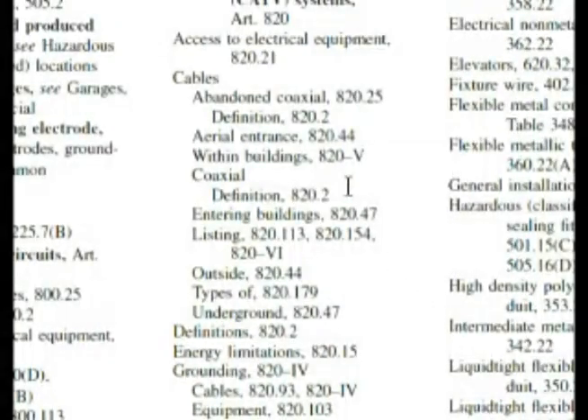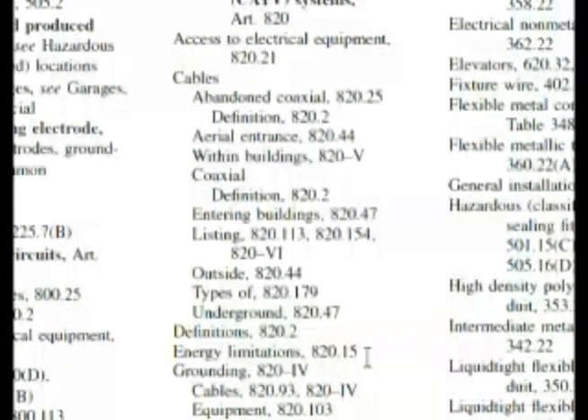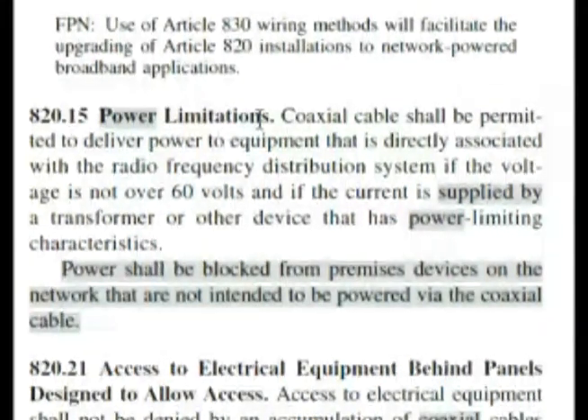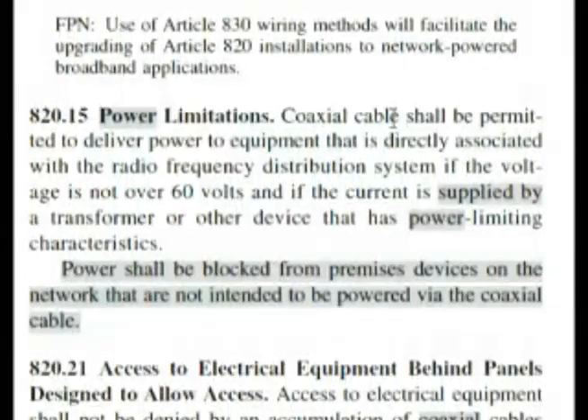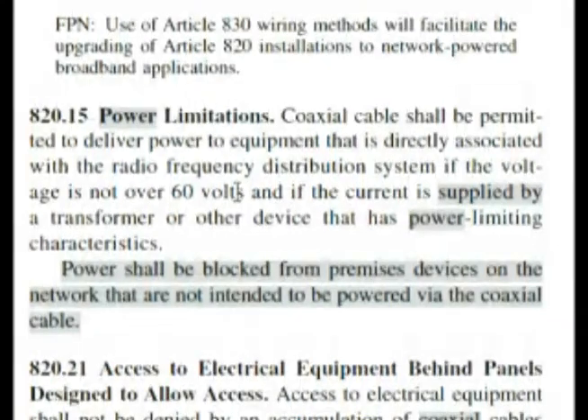Now remember when I said 'power limiting device'? Let's go down a little bit. As we're looking, here it is — energy limitations, 820.15. Here we are in our code book at 820.15 power limitations, and this is almost word-for-word: coaxial cable shall be permitted to deliver power to equipment that is directly associated with the radio frequency distribution system if the voltage is not over 60 volts — and the rest is word-for-word of our question.